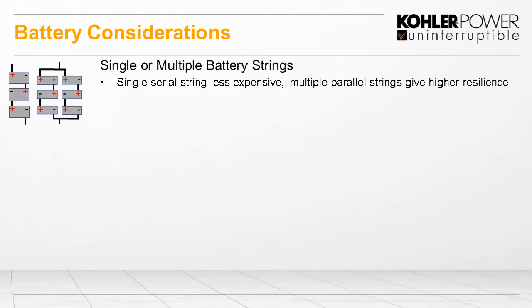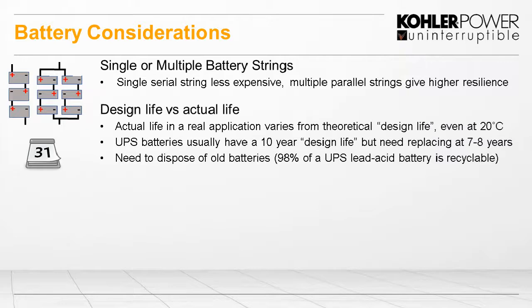So when we look at battery considerations and how we design the battery systems itself, we have either single or multiple battery strings. Now, the single strings are typically less expensive. However, they only have one string, so the resilience can be much lower. But having multiple strings with redundancy and resilience in there will cost you a little bit more, but tends to be a much better solution. Another thing that we get asked about quite often in a service aspect is the design life, which compared with the actual life.